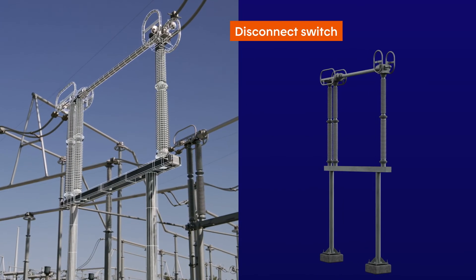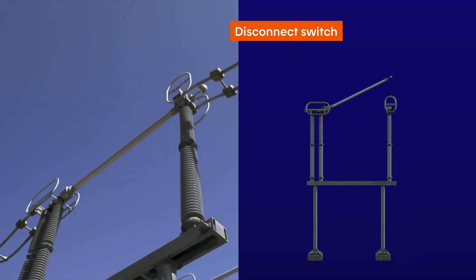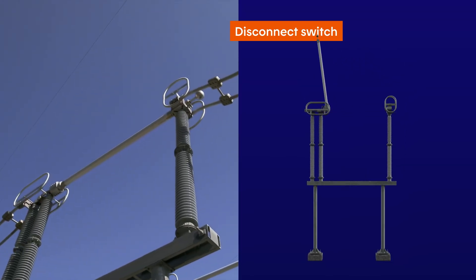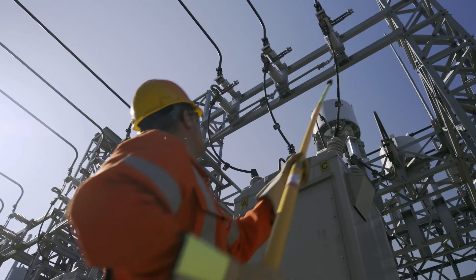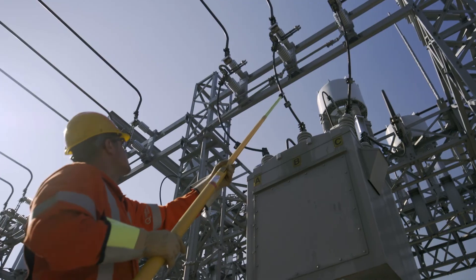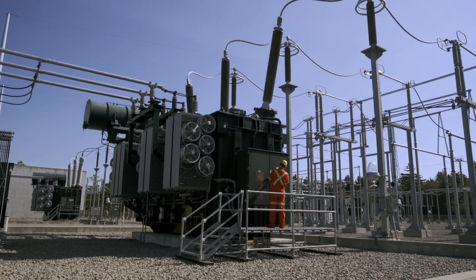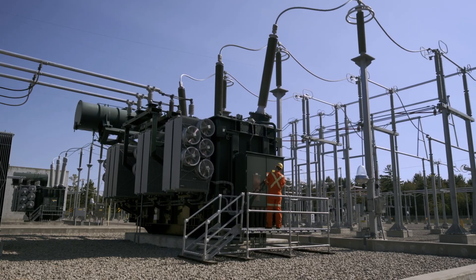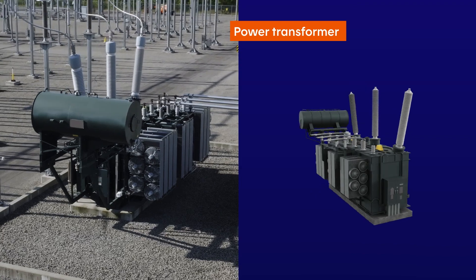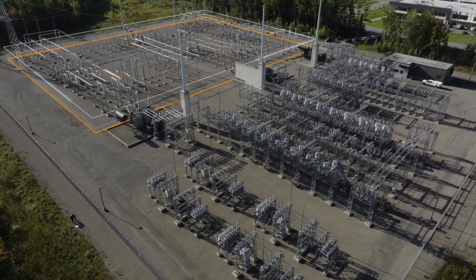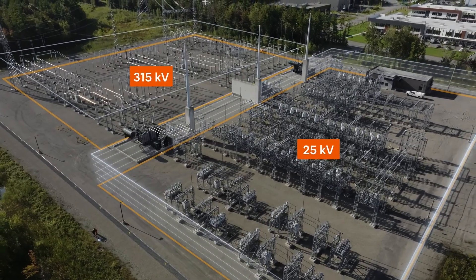The disconnect switch is a huge switch. It's easy to see if it's open or closed. It's used in different places to disconnect equipment from the grid or provide an alternative path for the electricity. The disconnect switch is essential to keep people safe. This is the power transformer — the heart of the substation. It's inside this giant green box that the voltage is raised or lowered. Here, the transformer lowers the voltage from 315,000 to 25,000 volts.